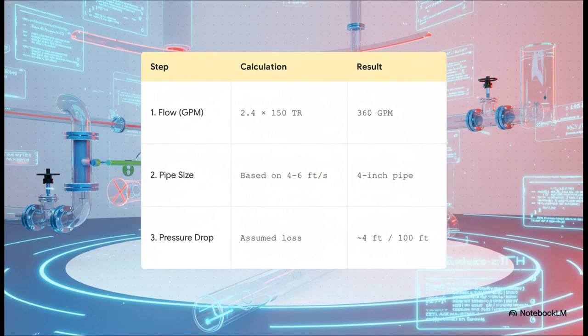Let's say we have a 150 TR cooling load. Step 1, we calculate the flow. We take 2.4, multiply it by 150, and we get 360 GPM. Step 2, we look at our engineering charts, and for 360 GPM, keeping our velocity in that 4 to 6 feet per second range, it points us straight to a 4-inch pipe. And for step 3, we check our numbers, and a 4-inch pipe with that flow gives us a pressure drop right around our target of 4 feet per 100 feet. Bingo! The design checks out.